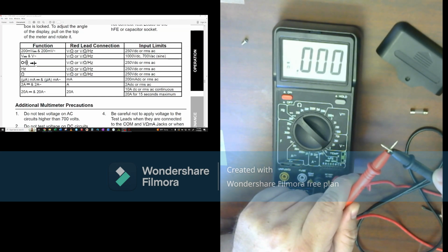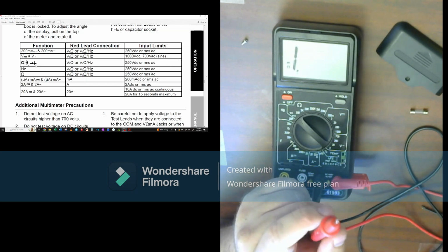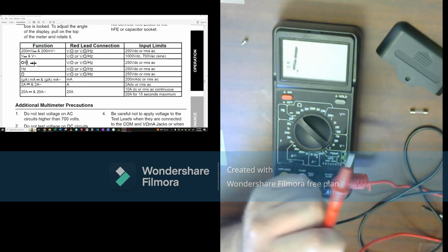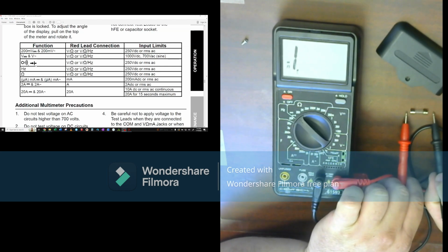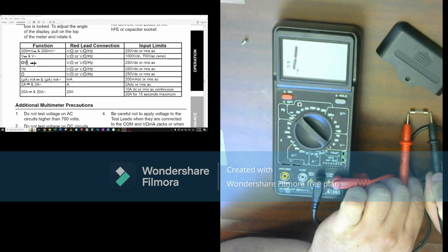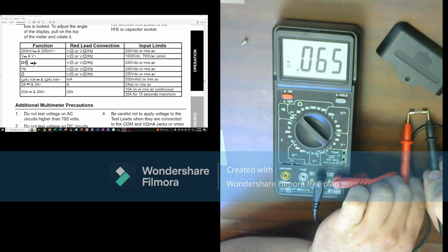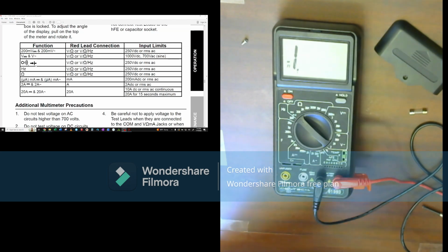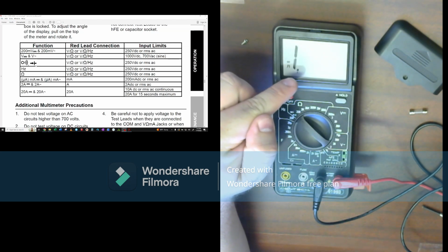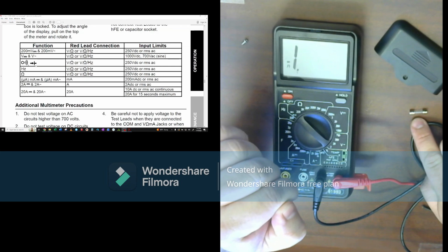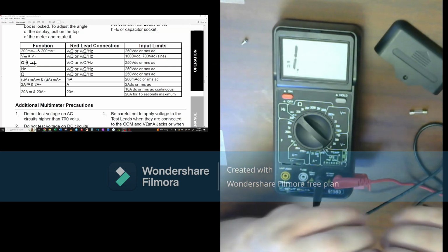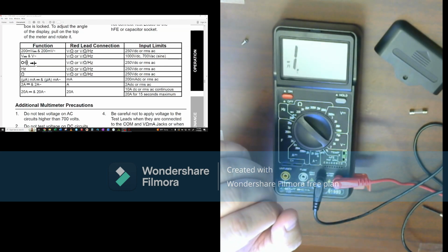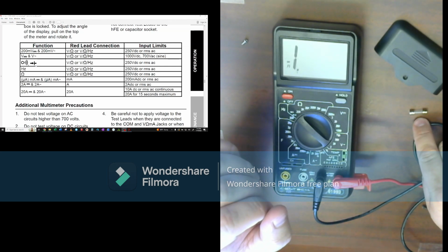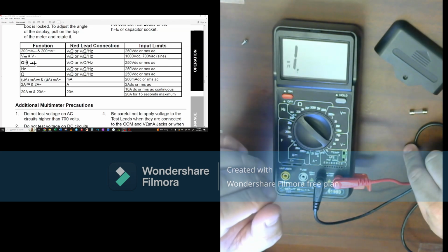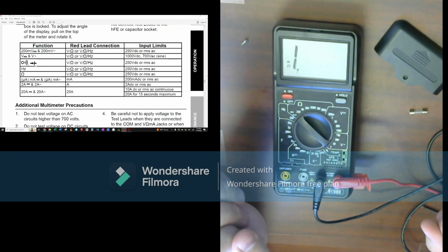Now, whether they're supposed to be connected together or not, that's my job as a technician to figure out. Should it be touching? Should it not be touching? When I'm checking my fuse, this fuse should read as a continuous connection, meaning that it is not blown, that it's still a good fuse. If we don't get that noise and this value does not go to 0, that means this fuse is blown. The little filament inside has exceeded the current and exploded, so there's no longer a connection in there. If that's the case, we need to take this out and replace it with the same type of fuse and put it back in. I'll show you how to reinstall the fuse once we're done.